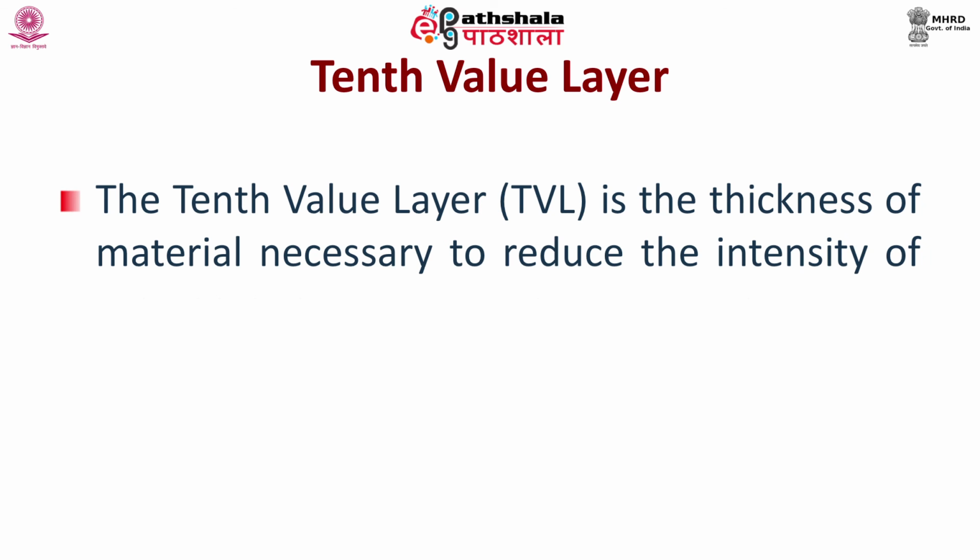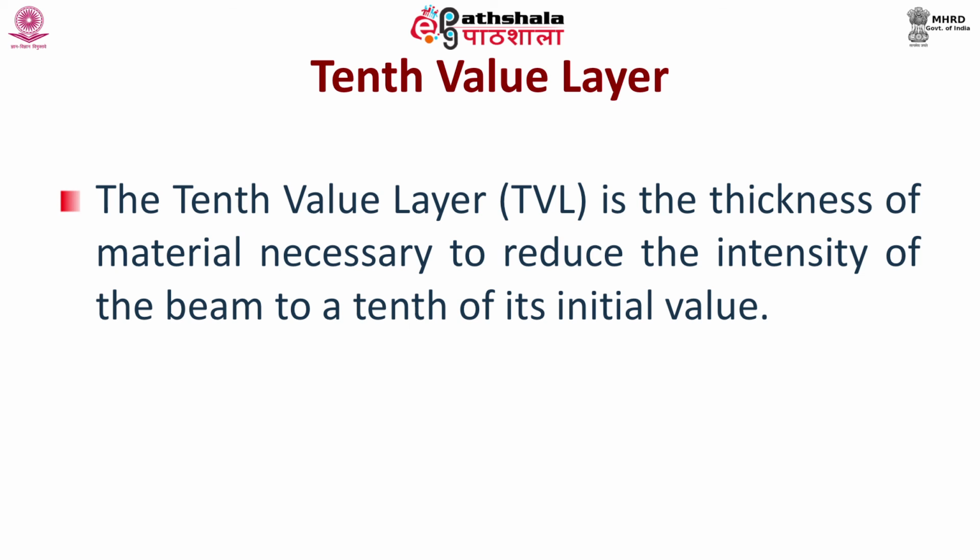The next term involved is the tenth value layer. It is defined as the thickness required to reduce the intensity of radiation to one-tenth of its original value. There is a relationship between the tenth value layer and the half value layer. The tenth value layer is approximately 3 times the value of the half value layer.